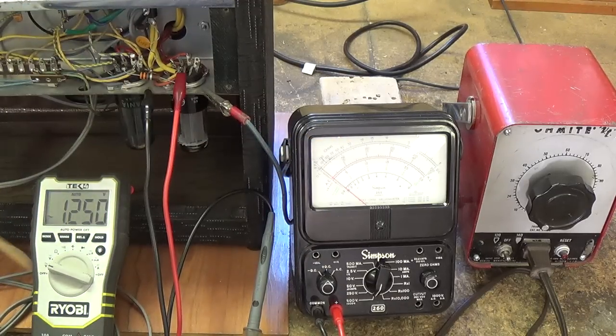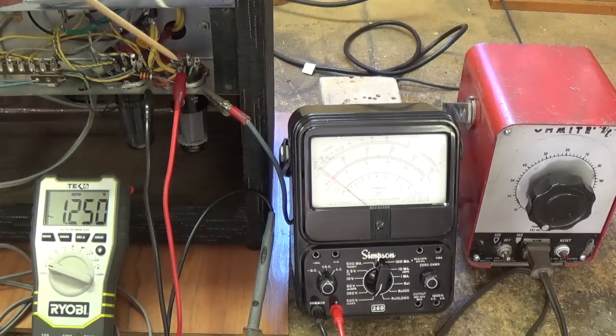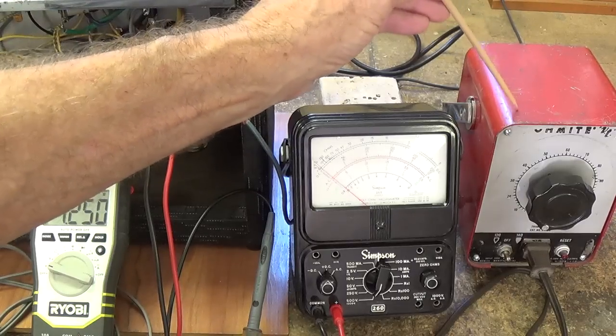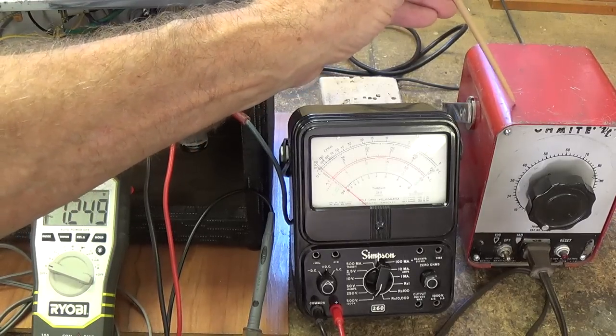Now granted, from zero to 37 volts, there was no output. So you could probably begin your variac warm up at about 30 to 35 volts.